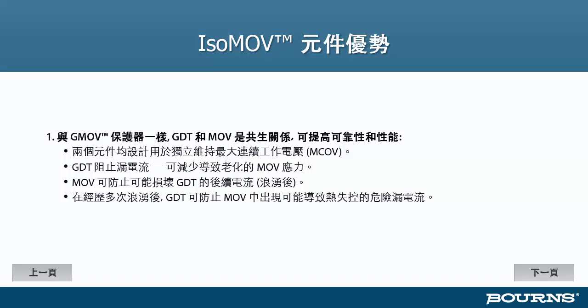Even after many surges, the GDT still prevents that leakage current, even though the MOV itself may be compromised. And that keeps the MOV from ever getting into the situation where a thermal runaway condition occurs. A normal MOV, towards the end of its life, starts to get more and more leaky, and that additional leakage causes dissipation in the MOV, raising its temperature. The increased temperature further increases the leakage current and leads into a runaway situation. Now that simply does not happen with the IsoMOV hybrid protection component, because the GDT prevents that dangerous leakage current from ever getting started, and hence the temperature never rises.